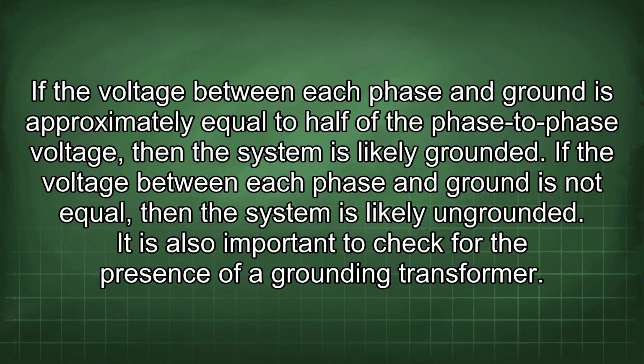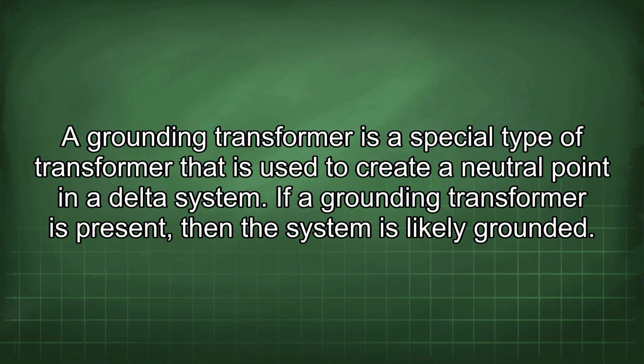It is also important to check for the presence of a grounding transformer. A grounding transformer is a special type of transformer that is used to create a neutral point in a delta system. If a grounding transformer is present, then the system is likely grounded.